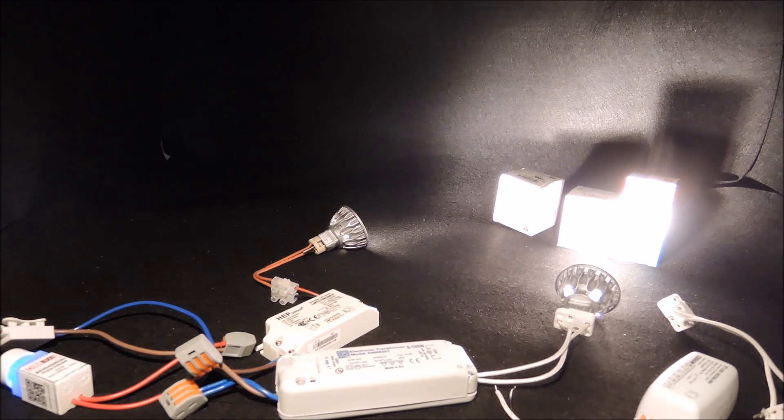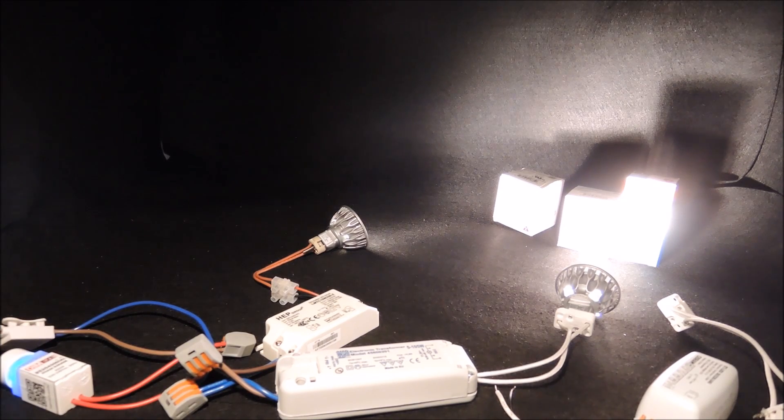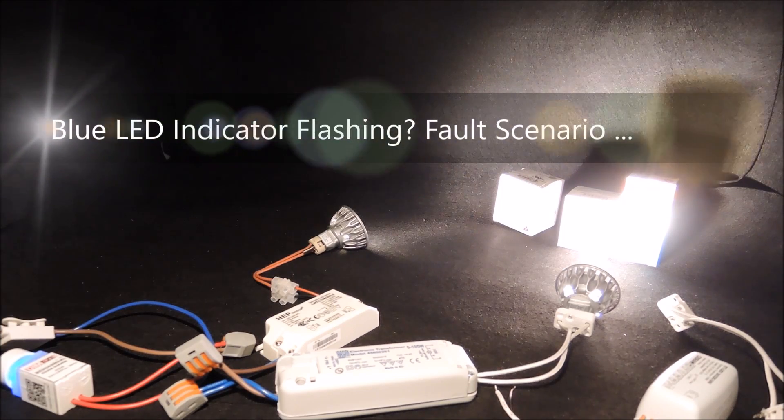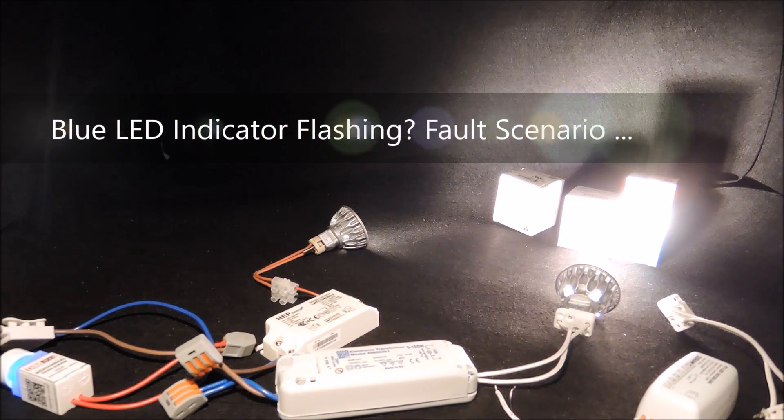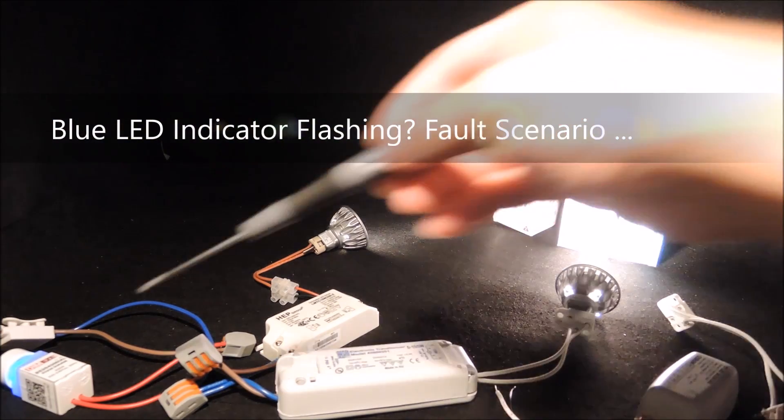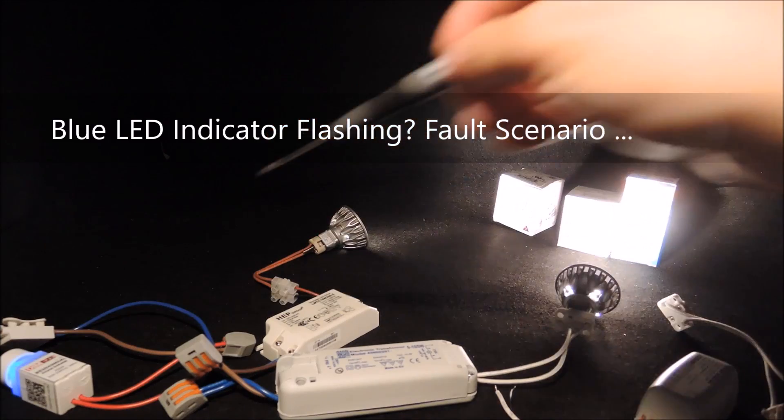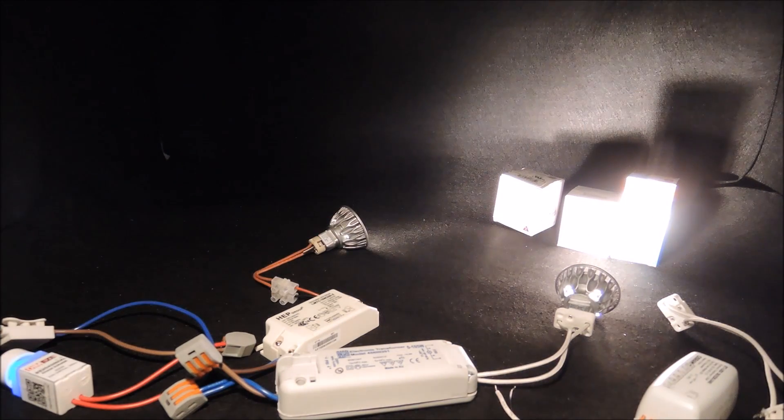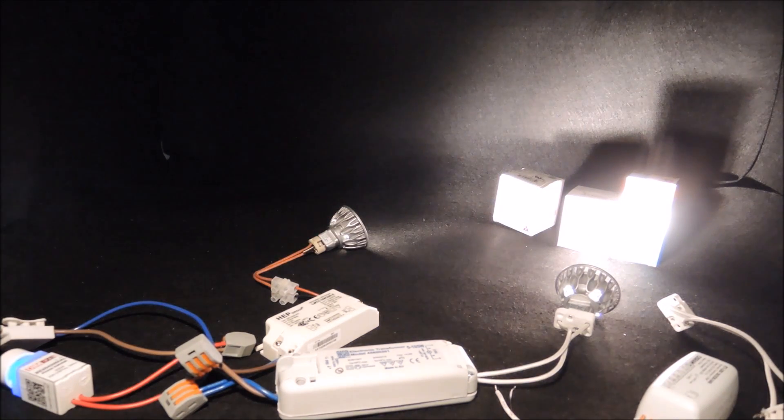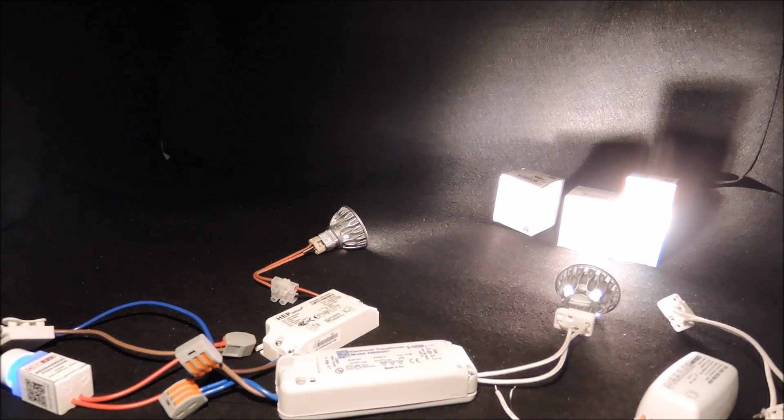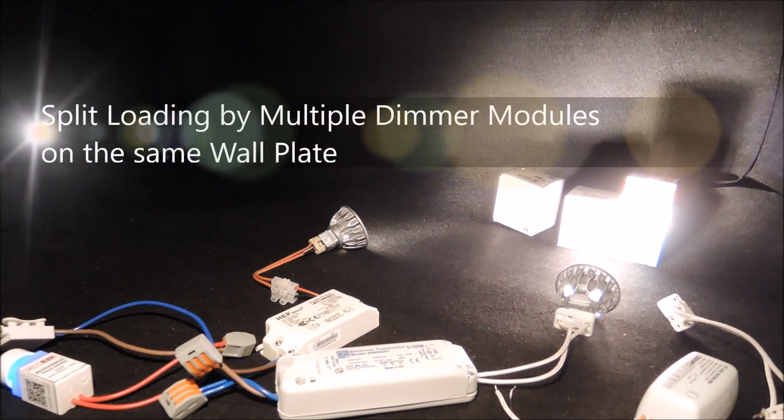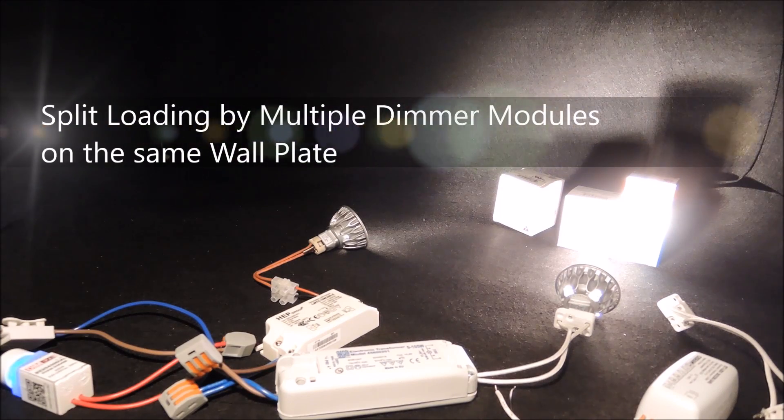In such cases, take note of whether our blue LED indicator would be flashing, which shows a fault scenario and can be a sign for overload. If overload, users are advised to split the loading and share by different dimmer modules.